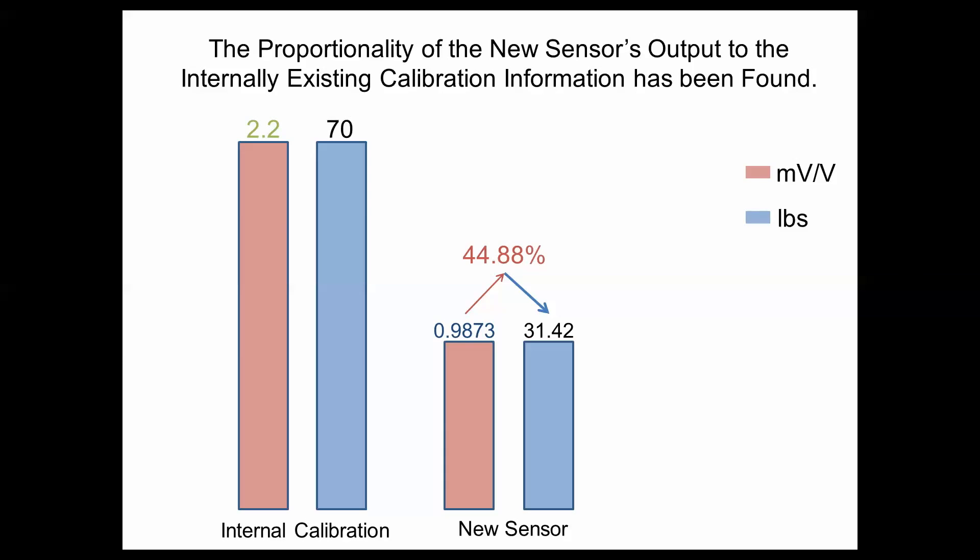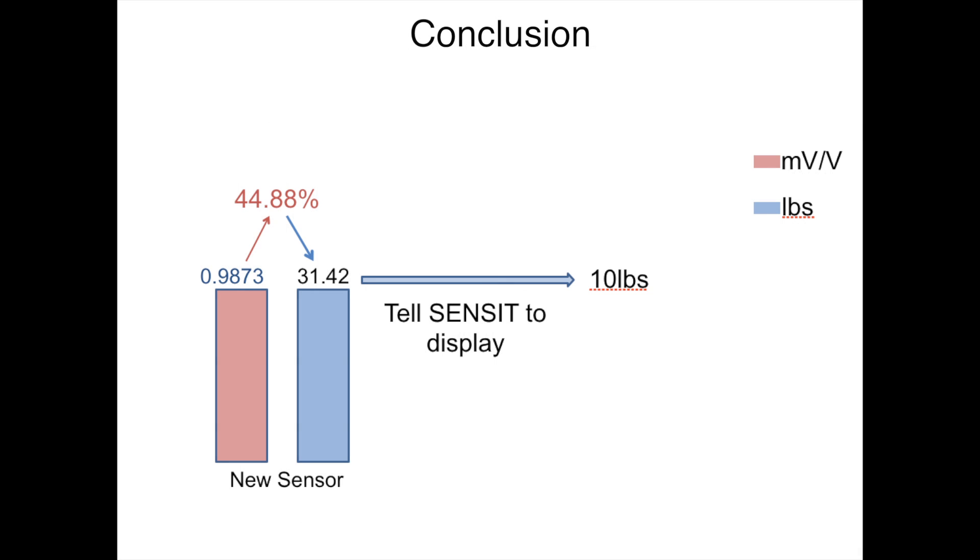As you can see, at 0.9873 mV per volt, which is 44.88% of the internal calibration line, is only using 31.42 pounds of the 70 pounds available. In conclusion, we use this 31.42 pounds to tell SENSIT to display 10 pounds as our new full capacity for our sensor.